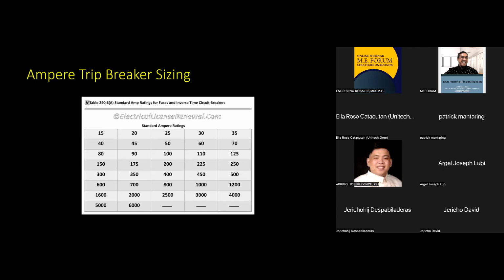Now, the lowest here at Unitech is a 20 ampere trip. The reason is, for the plans, so that we won't be given so much trouble by the municipality. The municipality does not allow less than a 15 ampere trip. Now, in Dumaguete, we use a 500 ampere trip for the ACCH, or air-cooled chiller. While for the pumps, I think I used a 175 ampere trip breaker.